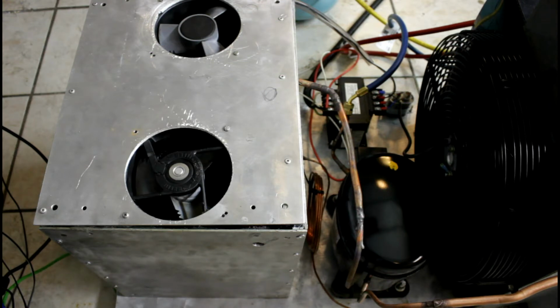The other real advantage of this, besides not having to deal with liquid getting on the electronic components, is that all the condensation will be on the outside, not the inside of the computer. Usually with refrigeration you think of insulating a CPU against condensation because the CPU will be colder than the air, but with this system all the condensation stays on the outside — it's completely dry on the inside, just like a refrigerator would be, and it drips out condensation through a condensate drain, which then evaporates.